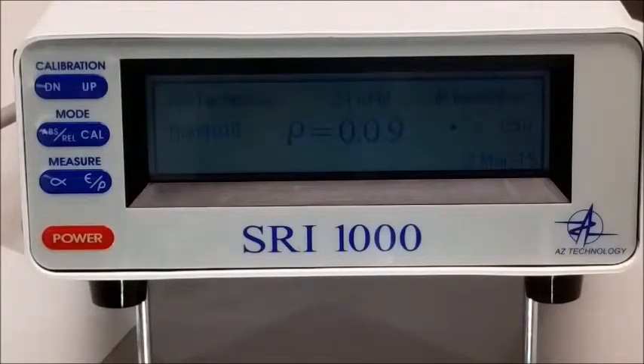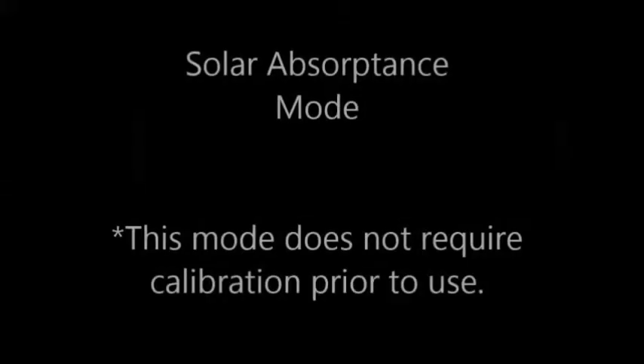One should also replace the gold calibration sample and see if the same is true for the gold. If the measured values seem to be varying around a value that is not within a few points of the appropriate values, one may wish to repeat the calibration process. Step 8. Once calibrated, replace the screw caps on the calibration samples and store appropriately. Solar absorptance mode.